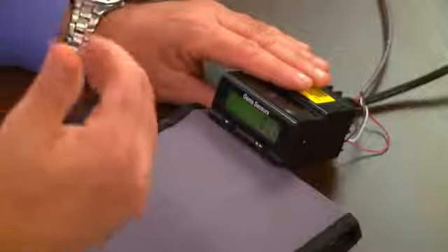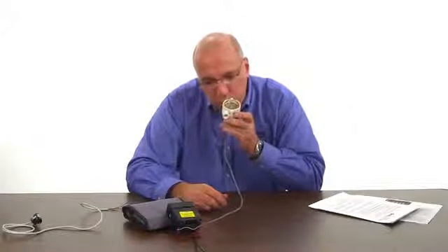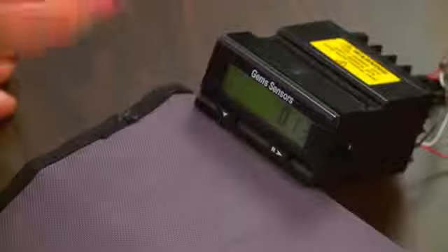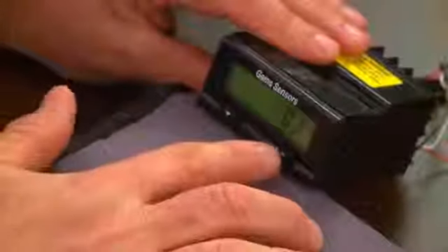Right now it's in the count mode, in the totalization mode. It will just increment upwards forever and never stop. The other mode is the rate mode. If you sever the jumper on the back for the calibration mode, you never get back into the calibration again, and all the customer has access to, or your end user has access to, is just the button on the front to toggle between total and rate. Let's blow through the sensor, and you'll see that the number will just increase in a positive manner. So this is how many gallons would actually be going through the sensor. The sensor's made it up to about 0.13 or 0.14. And because I have step number 6 on, I can reset it back to 0.